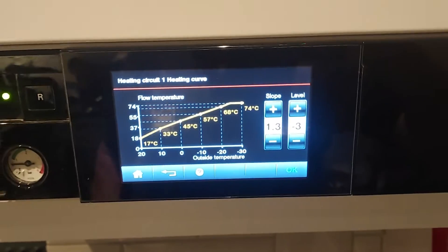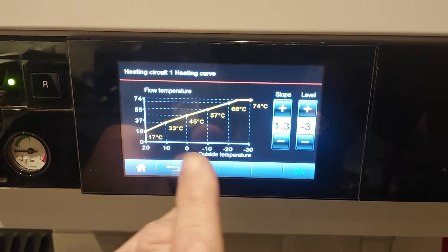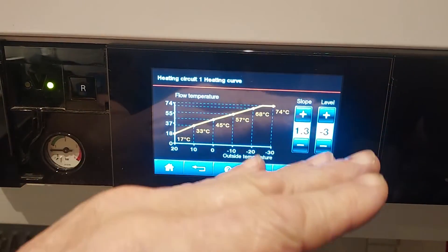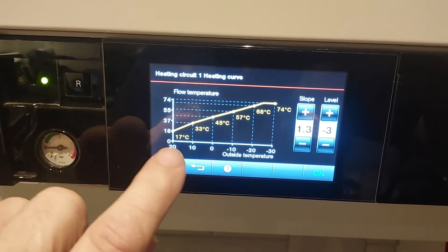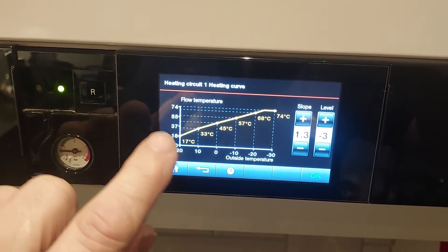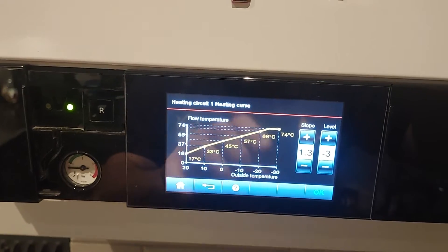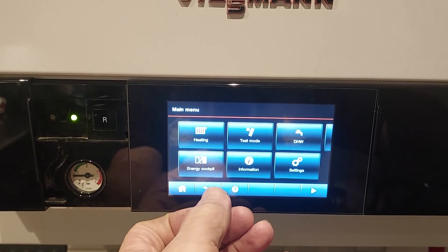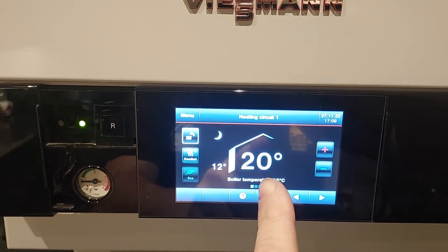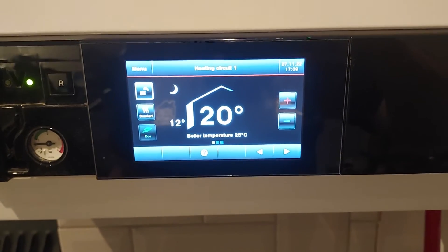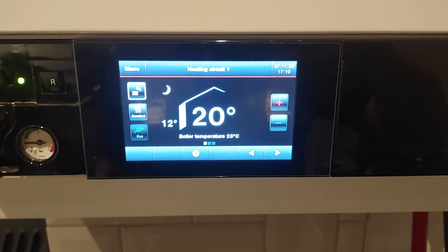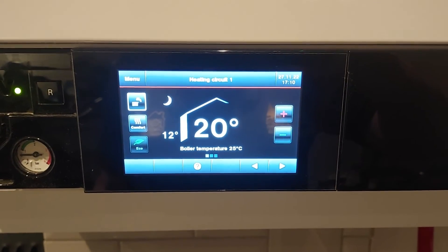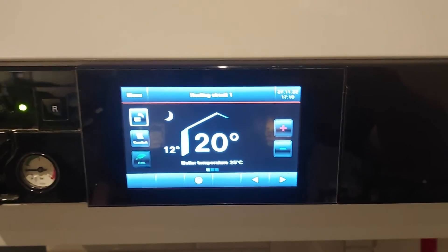So this level adjustment does exactly the same thing as adjusting the actual set temperature for the room — it's the same adjustment in effect. On the graphs it's normally shown as a horizontal line with the room temperature set on it. I've adjusted the overall curve by adjusting both the slope and the level. I hope that's clear and I hope it helped.